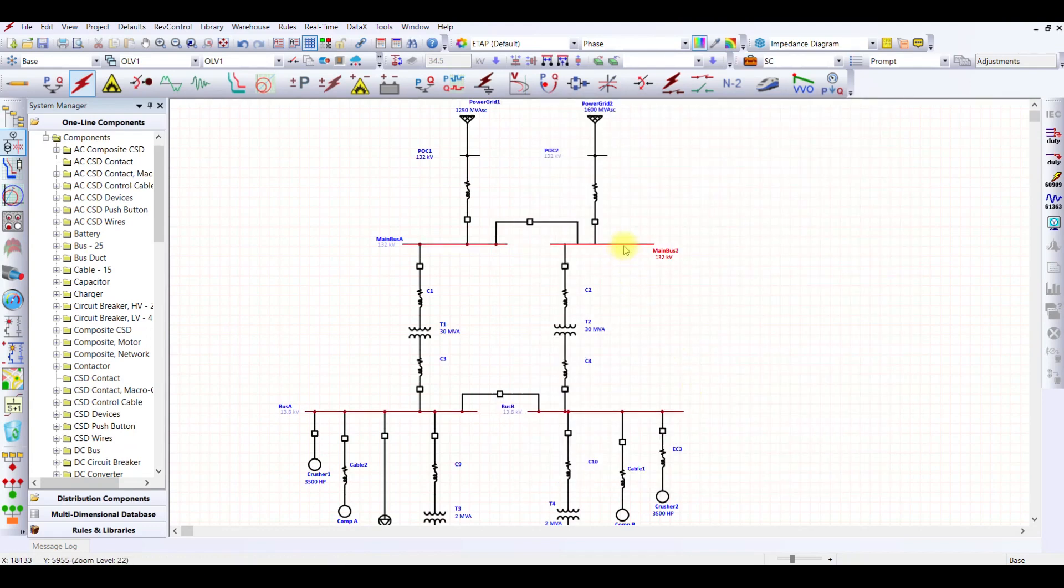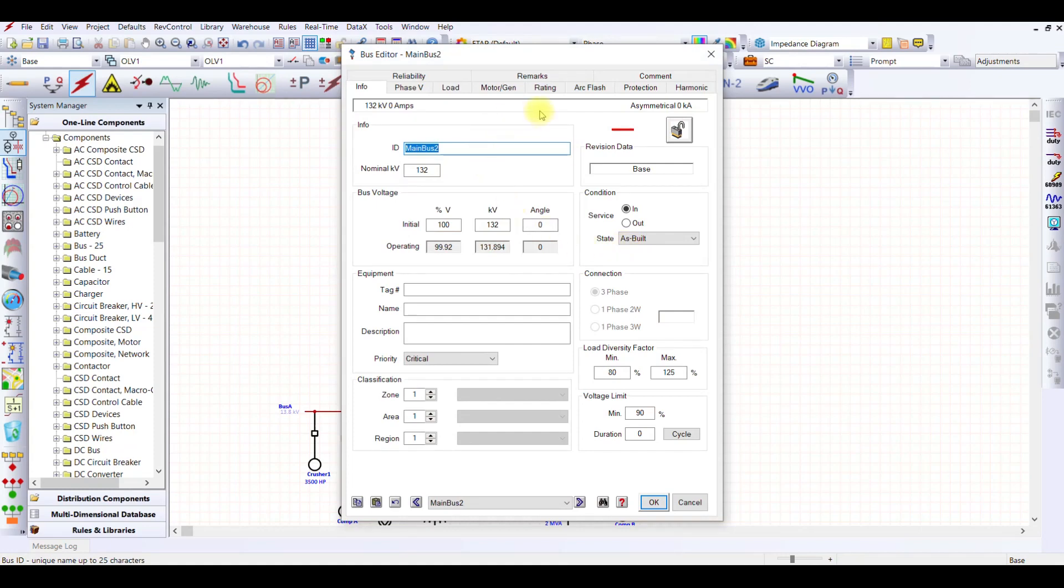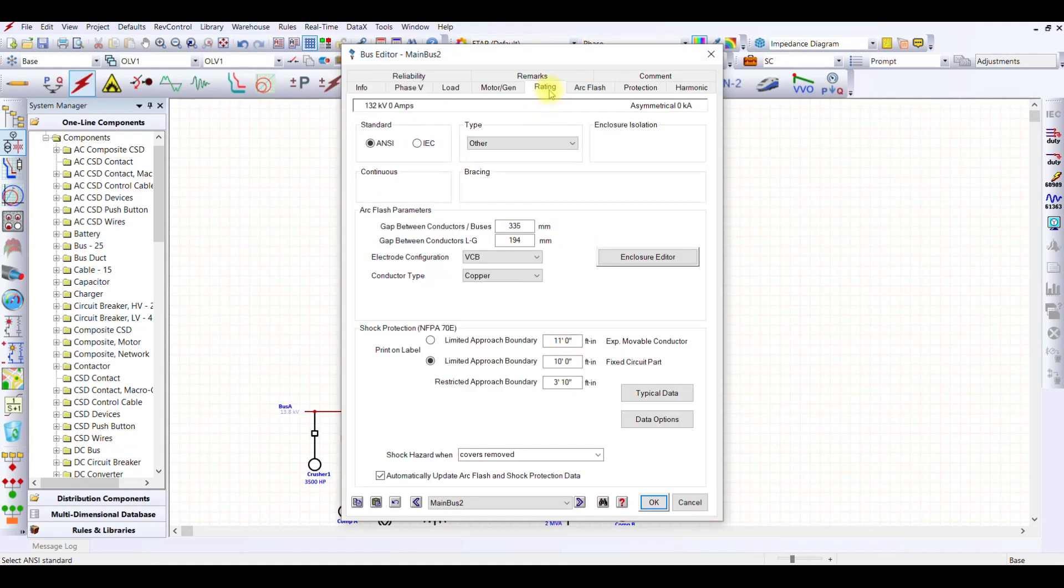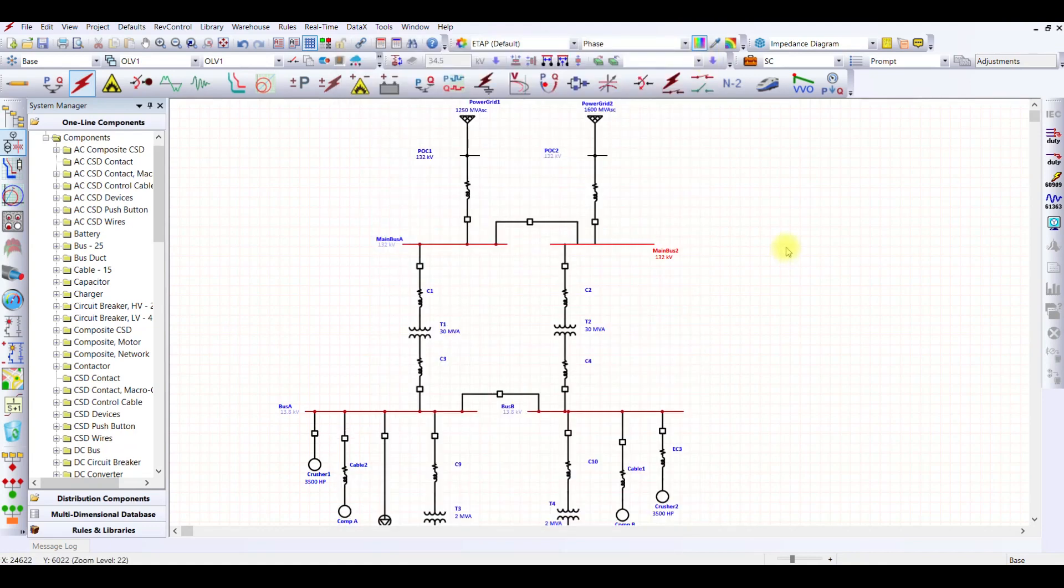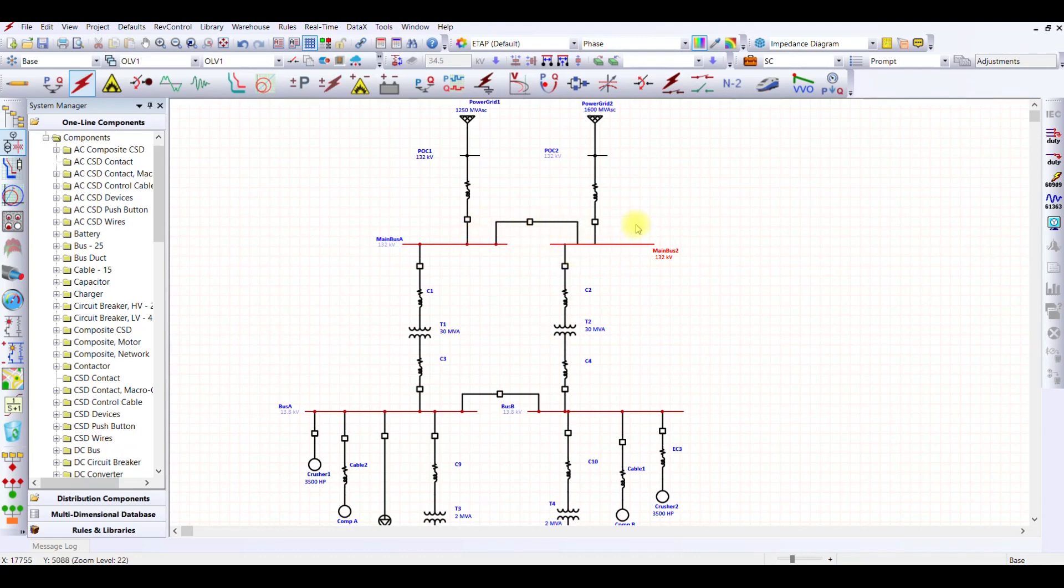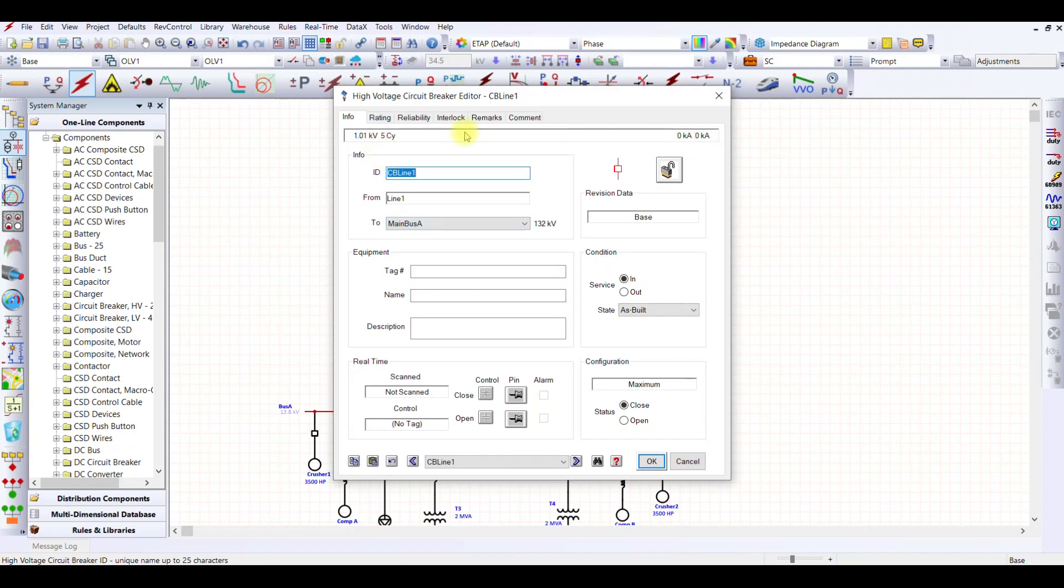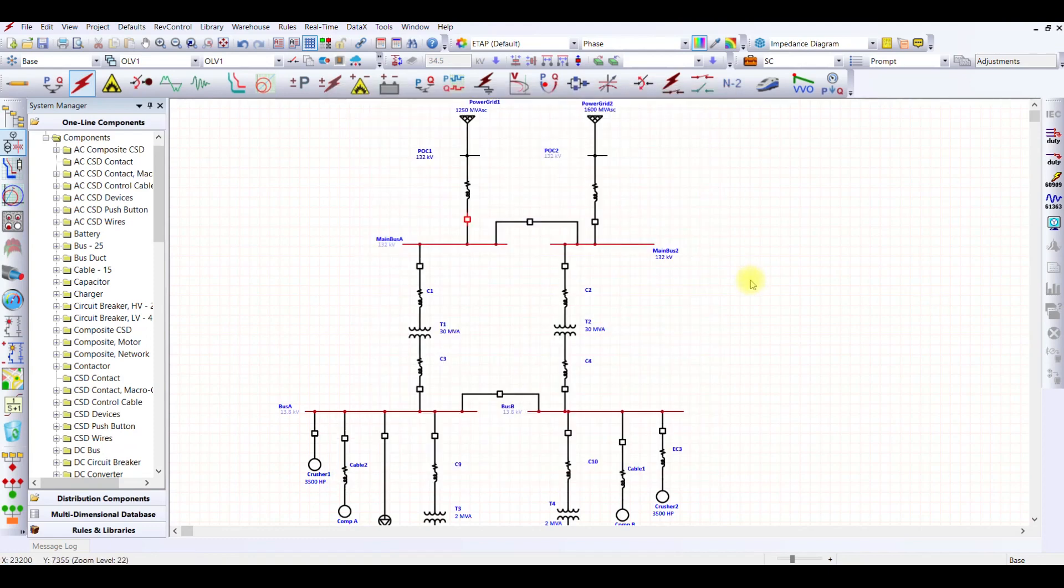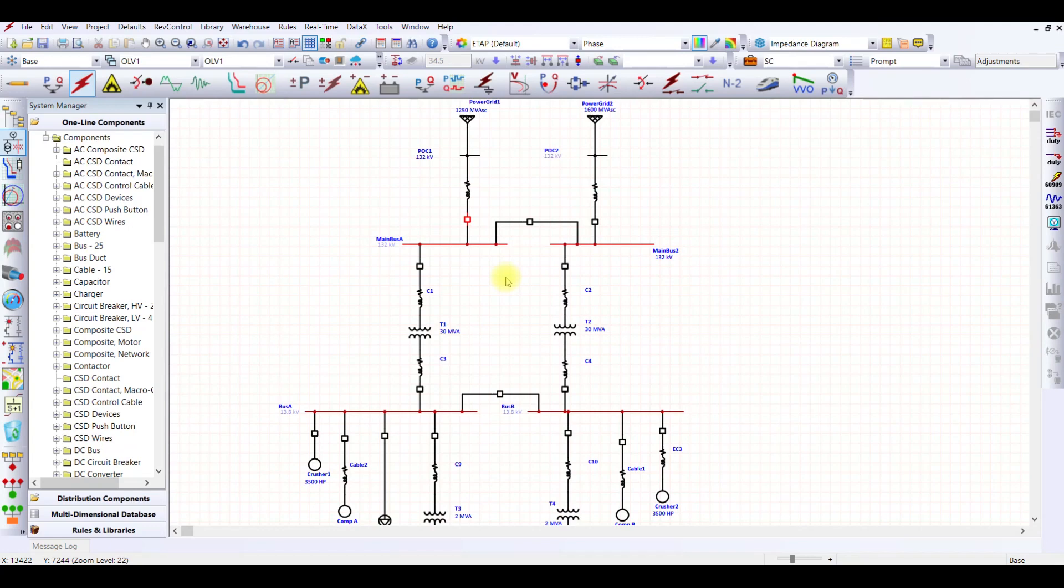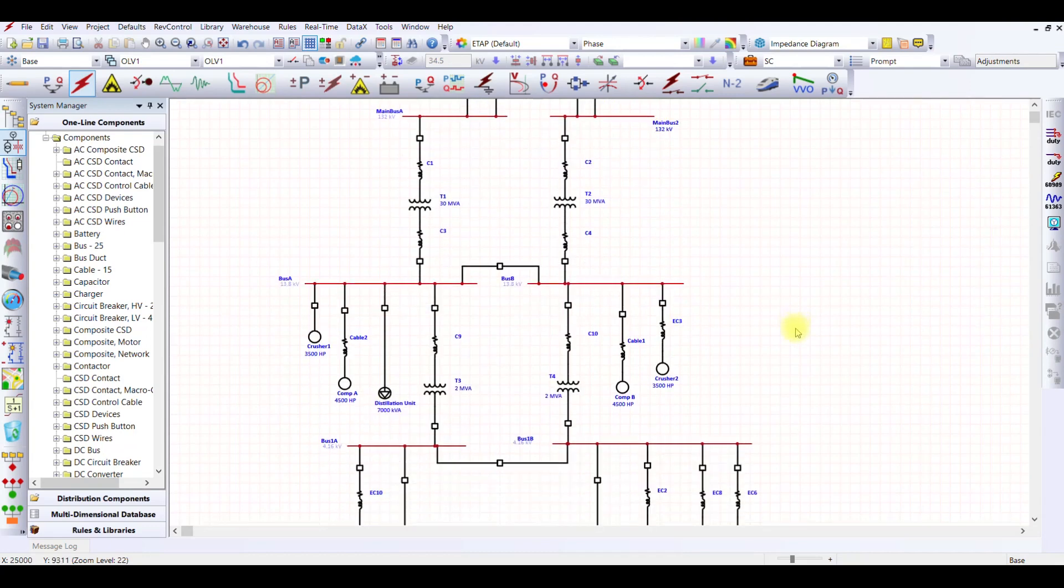Similarly, for alert, alert is going to tell me my alert based on the equipment capability. But if I press OK here, if you see, if I double click on my bus and if I go on my rating, I haven't provided any kind of rating for here. I haven't provided any bracing rating. Asymmetrical 0 kilo ampere. I haven't provided what kind of kilo ampere I can have on my bus bar. This is exactly what I want from the planning stage. What I want to make sure is that what should be the capability of number one, my buses, and secondly, my switchgear or circuit breaker. If you see the circuit breaker here, here you see 0 kilo ampere, 5 cycle 0 kilo ampere. What I have done is I haven't included any kind of requirement for the circuit breakers as well. I do not know because this is the planning stage and I do not know what will be the exact short circuit current in my system. So I do not know what kind of capability device capability I should select. That is exactly the reason why I am performing short circuit analysis.